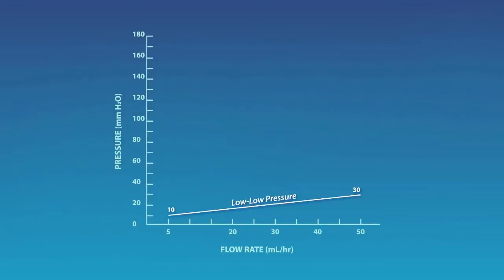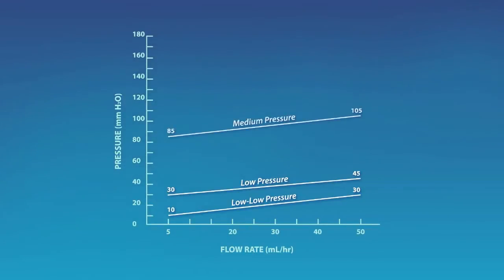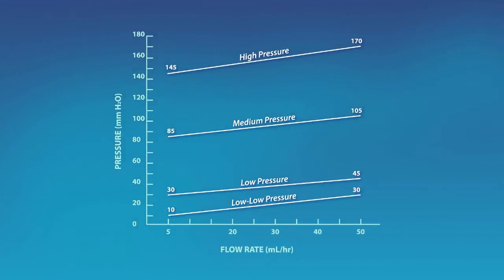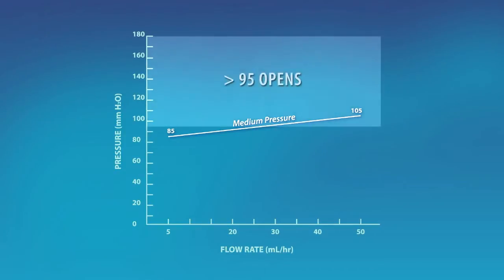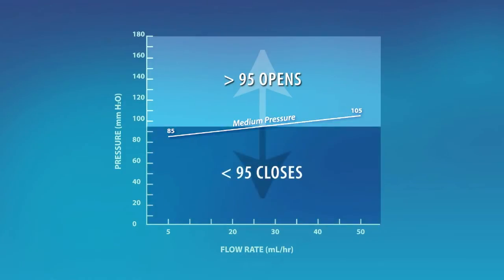The pressure flow graph shows the threshold at which the membrane will open for each pressure level at various flow rates. These levels are determined by the midpoint on the pressure level range at the typical CSF production rate of 20 to 25 milliliters per hour. For example, if a surgeon is using a medium pressure valve at an average flow rate of 25 milliliters per hour, the valve will have a nominal resistance of 95 millimeters H2O. Therefore, when the ICP is above 95 millimeters H2O, the valve opens and drains. When the ICP is lower than 95 millimeters H2O, the valve closes.